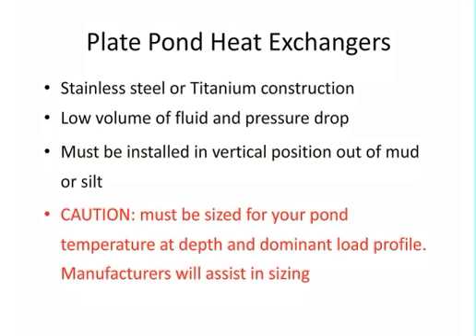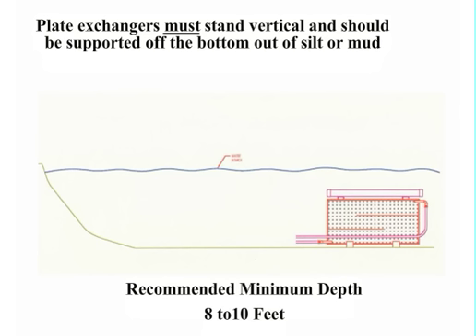That has been an issue. Some manufacturers will rate their plates at the BTU heat of rejection, and when you bring that size plate up into the northern heating dominant climates and you start to get into that cold water, you don't have enough heat exchanger in there to support that particular size in that environment. So make sure if you're going to apply these plate heat exchangers, you're working with that manufacturer to ensure that it is sized correctly for your location. So here's an example. Again, the plate heat exchanger must stand vertical and up off the bottom. Again, making sure you have that minimum depth over the top of the heat exchanger. You don't want to be affected by the elements going on outside.